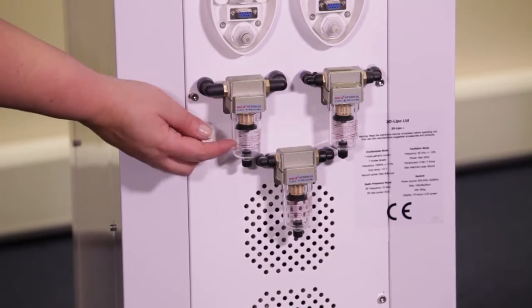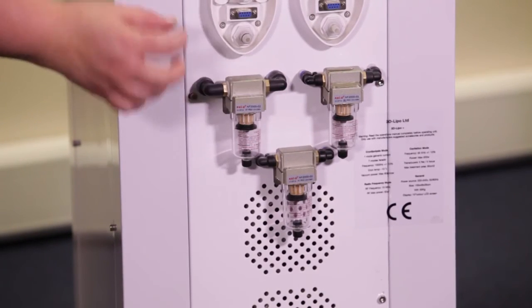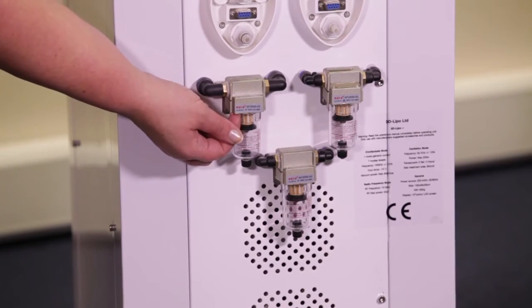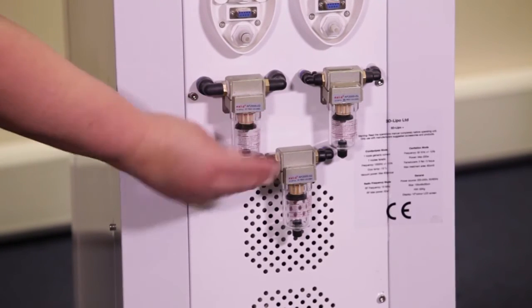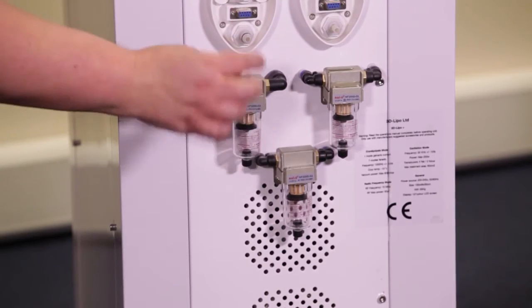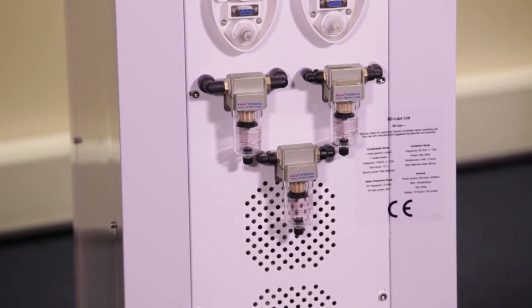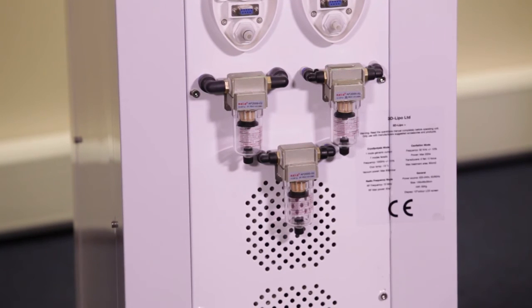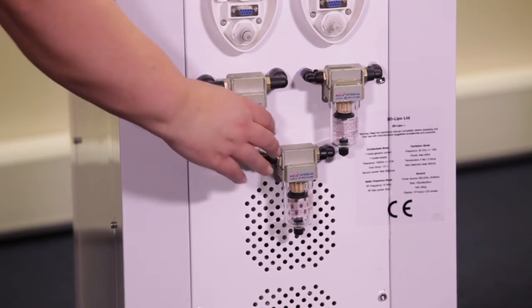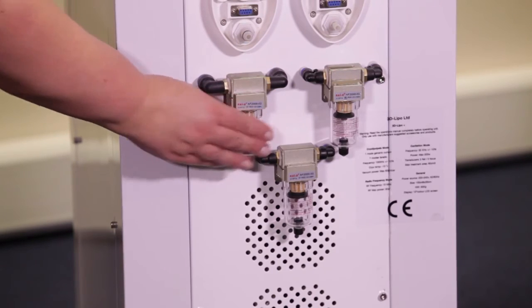Do make sure though that you find your O-ring that will sit sometimes inside the gold box here. Unscrew the filter, take your O-ring out, but make sure your O-ring sits on top of the filter when you screw it back in. If your filter is not in tight enough or the O-ring is not in place, you will lose vacuum on your cryo attachment and your vacuum roller. So just make sure when it's put back in, it's nice and tight.